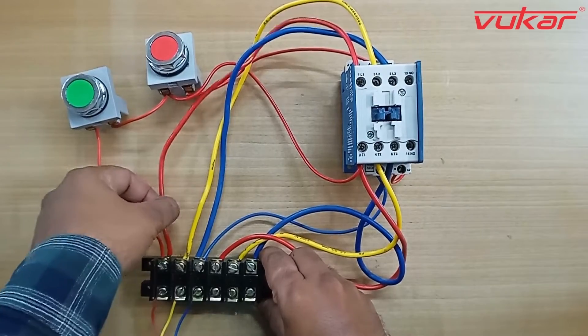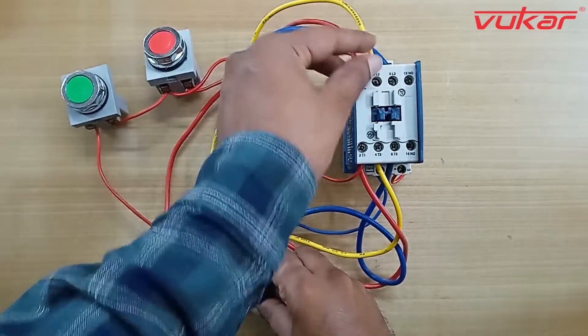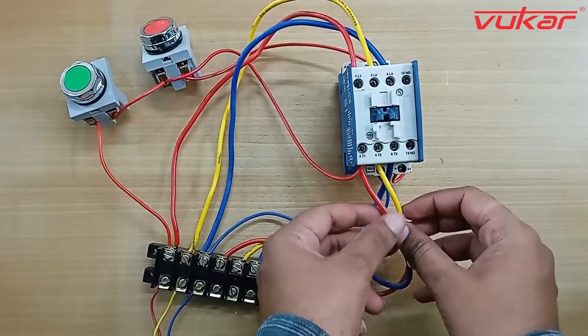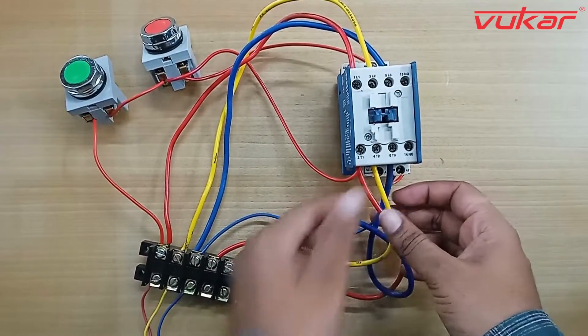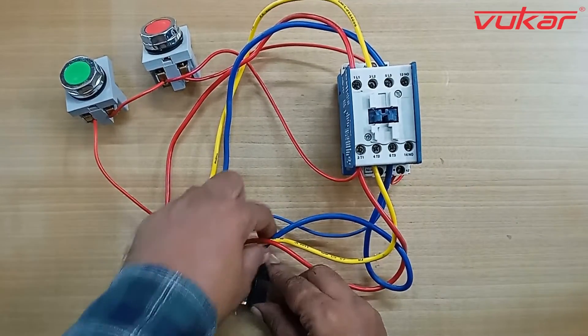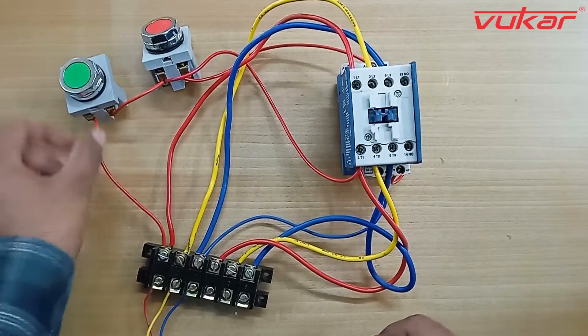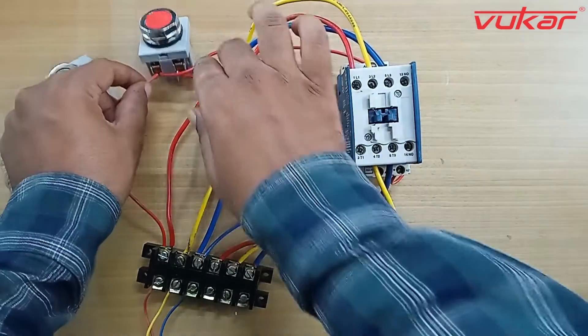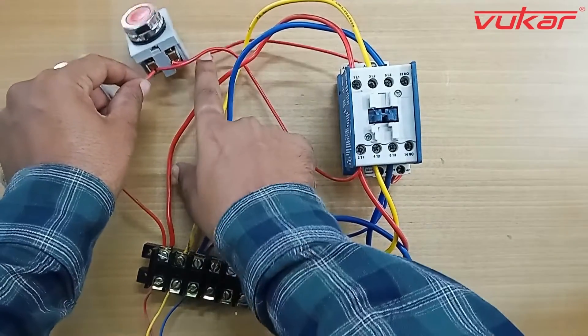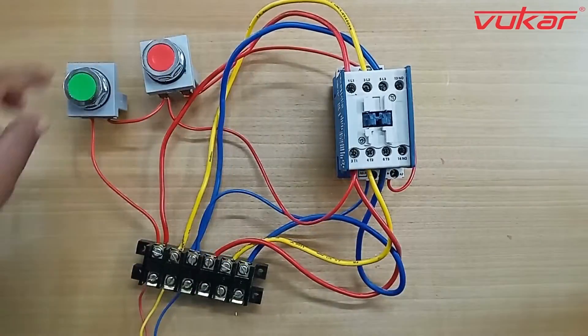Now connecting the control wires as explained before, you can also see that the input terminal and output terminal of the contactor, 2.5 square mm wire or 4 square mm wire is used. For control wiring, you can use 0.5 square mm wires.